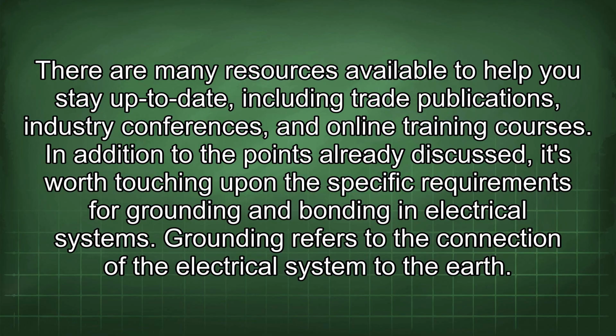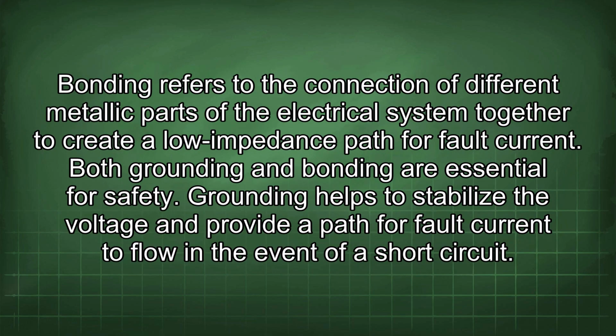In addition to the points already discussed, it's worth touching upon the specific requirements for grounding and bonding in electrical systems. Grounding refers to the connection of the electrical system to the earth. Bonding refers to the connection of different metallic parts of the electrical system together to create a low impedance path for fault current. Both grounding and bonding are essential for safety.